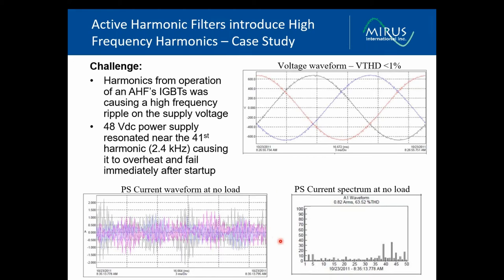As I went in and looked at the spectrum, you could see that there was harmonics up around the 39th to 43rd harmonic. This was being drawn into the tester by that power supply, and you can see this high-frequency currents at no load. So there was a resonance between this power supply on the tester and the high-frequency ripple introduced by the IGBTs of the active harmonic filter.